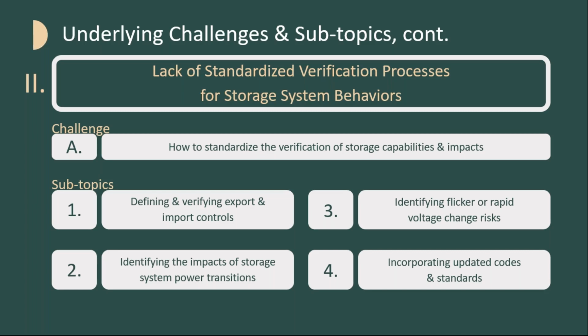The first item is defining and verifying export and import controls. Storage systems are flexible and can change their output level. Through the interconnection process, or for other reasons, you might need to limit the output or export level across the point of common coupling into the distribution system. That could limit impacts on the distribution grid, even if your storage system, or storage plus solar system, could output more power. You might also decide to limit import values for charging purposes.